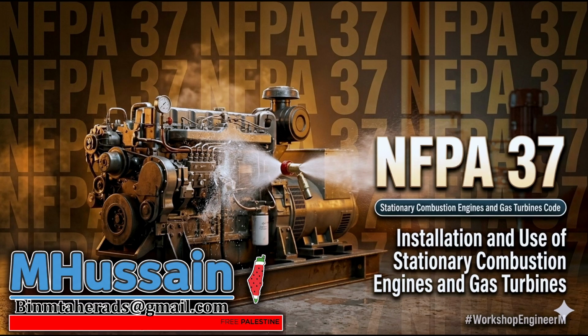Yes. So when the fire alarm trips, the engine has to shut down, the fuel valves have to close, and those massive louvers have to slam completely shut and form an airtight seal. And if they don't seal perfectly? The suppression system dumps tens of thousands of dollars of clean agent gas into the room, and the residual airflow just blows it right out into the parking lot. The fire just keeps burning. Even if they do seal, there are tiny microscopic leaks everywhere. Conduits, door frames. The gas slowly escapes.